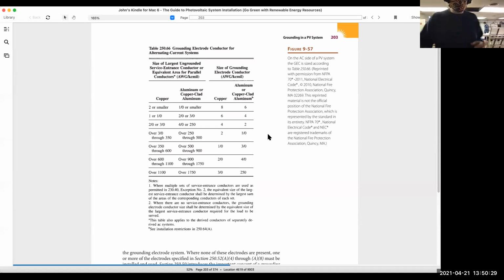When we're trying to pick our ground wire, we have to pick our copper wire, whatever the size is. Bigger is always better, but if we're running number 6 or number 2 wire, we might want to run a number 2 gauge. But it says number 2 or smaller. It also shows that your grounding electrode is not going to get smaller than a number 8 or a number 6. We buy number 8 grounding electrodes, copper grounding electrodes, all day long. Go to Menards and try to find one.